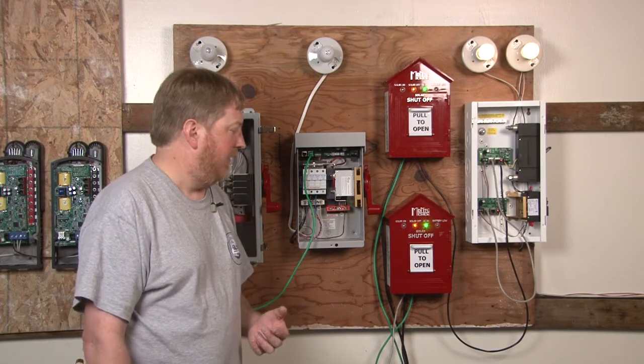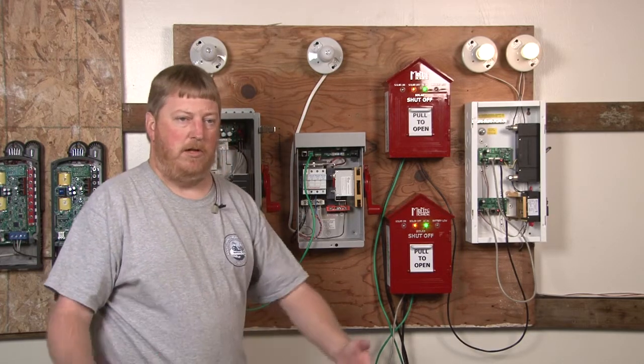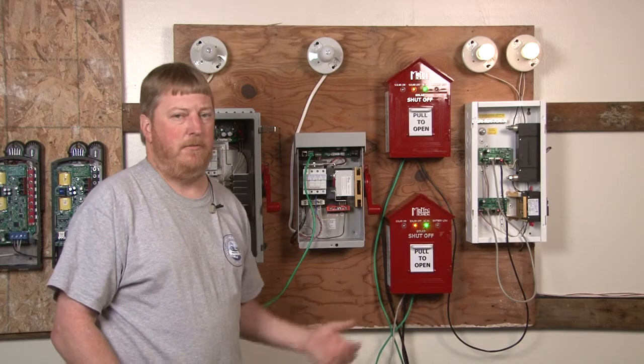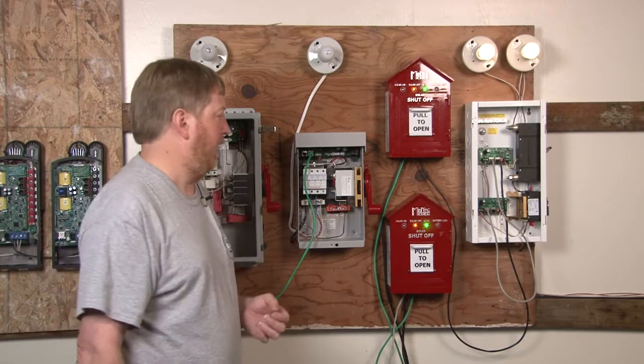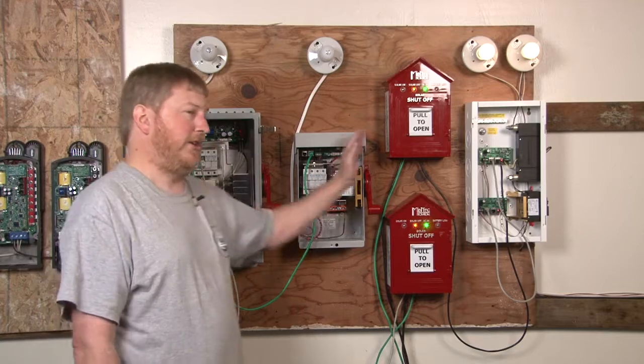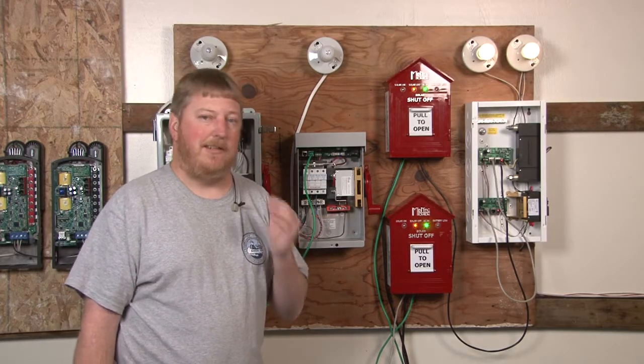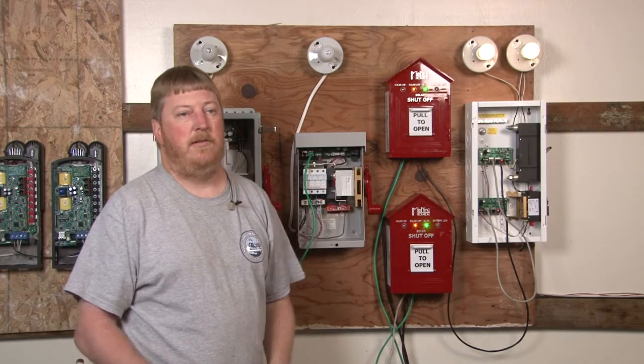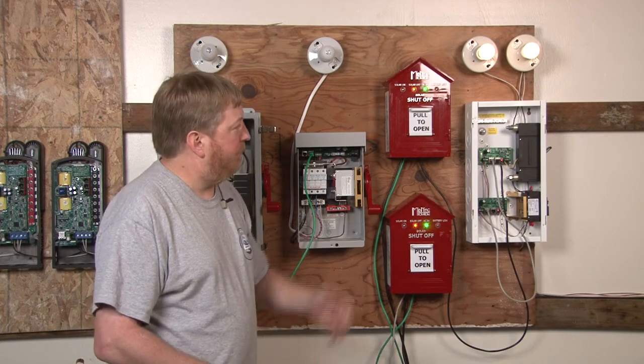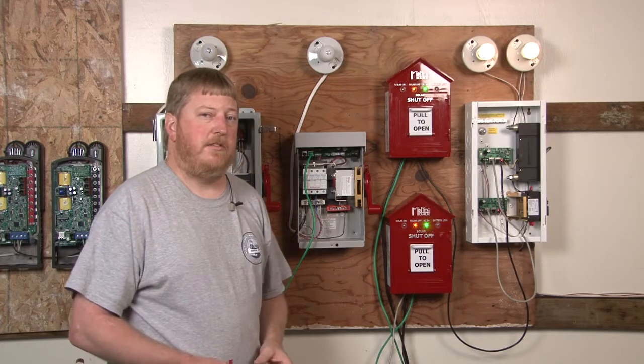Again, if I'd have cut the cable, it would shut the whole system down because it would assume either vandalism or fire or outside source, maybe a mouse has chewed through the wire. We don't know the case. If the cable's unplugged, we only shut down what's upstream. If the cable is actually damaged, we shut the whole system down. It's a pretty quick rundown of the rapid system shutdown.